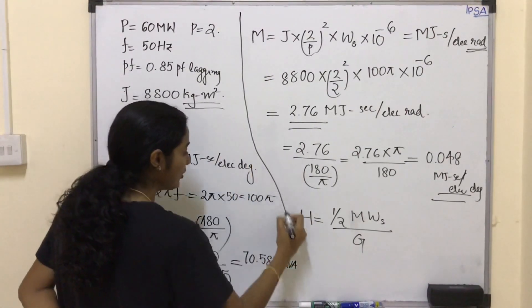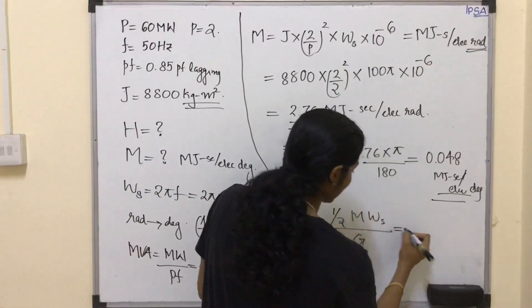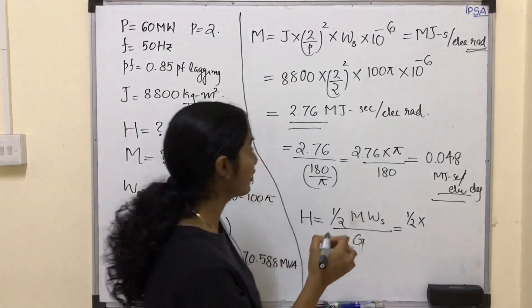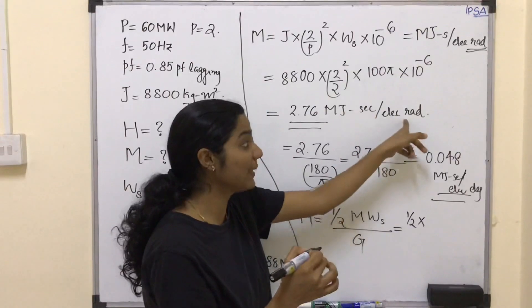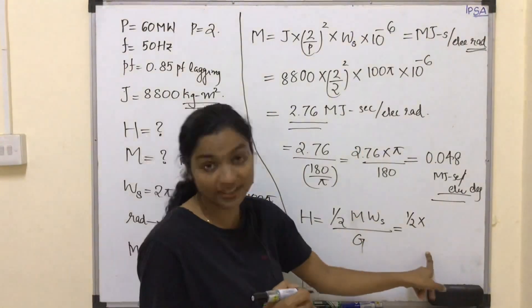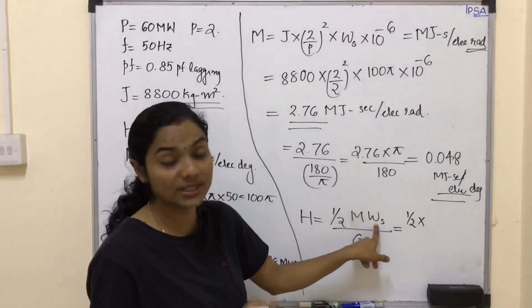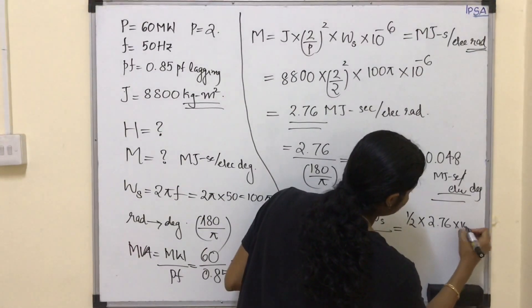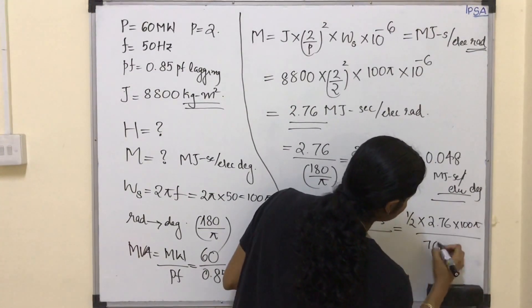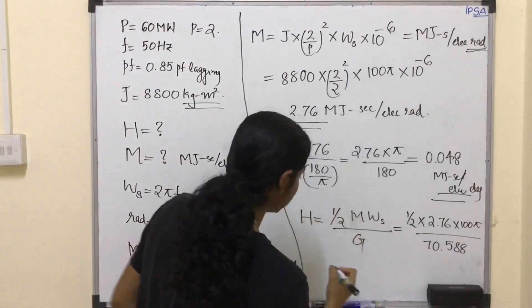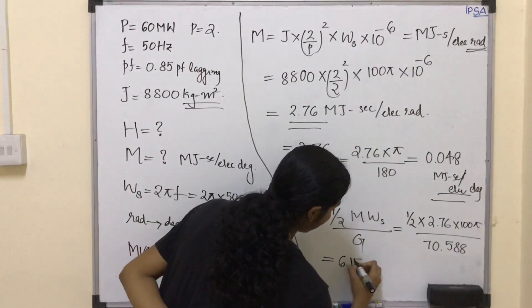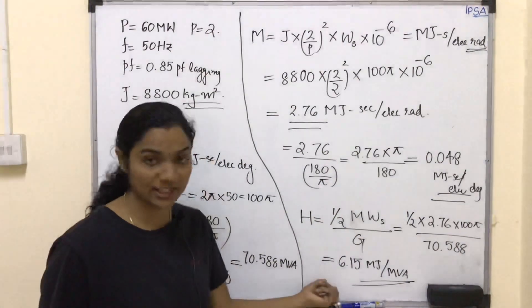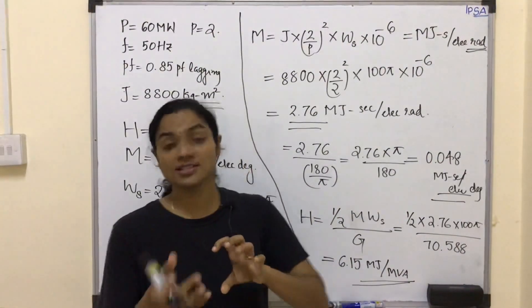Substituting the values: H equals half multiplied by M (2.76 MJ·s per electrical radian) multiplied by ωs (100π), divided by G (70.588 MVA). This gives H equal to 6.15 MJ per MVA.